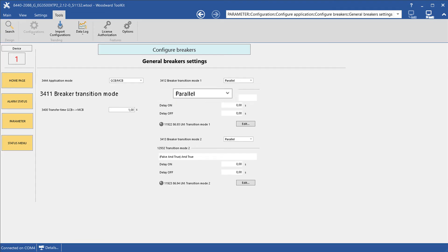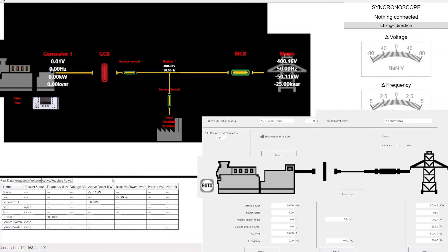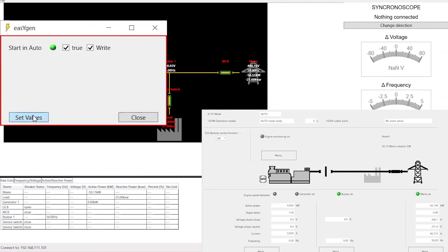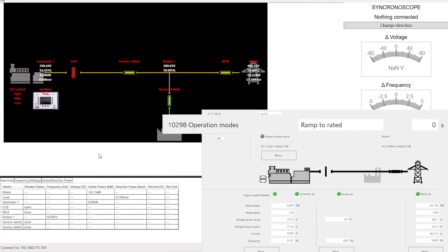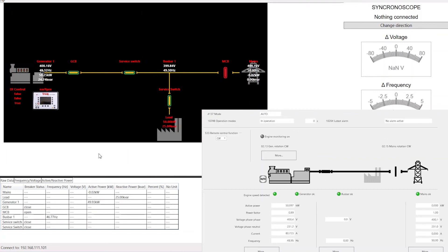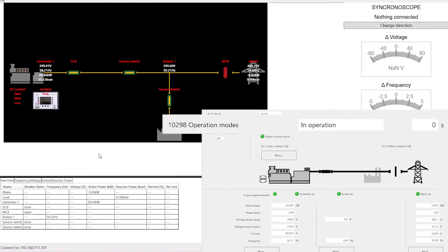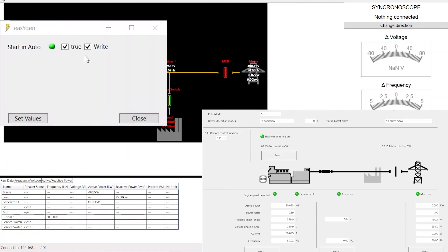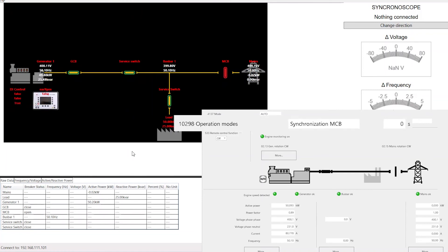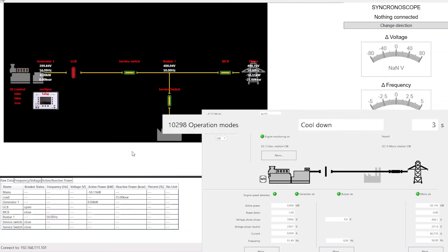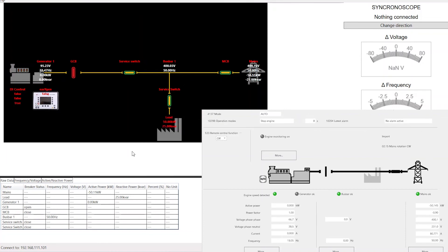The next breaker transition mode is closed transition. Again, the load is supplied by mains. When the genset receives a start command, the engine starts up and the generator ramps up to its rated values. When rated values are reached and monitoring is activated, the GCB is synchronized and the mains breaker is opened immediately after the closing of the GCB. The EasyGen is able to match a breaker closing time of less than 100 milliseconds. Now the load is fed by the genset. When the start request is removed, the EasyGen synchronizes the mains breaker and immediately opens the generator breaker. As we are only short time parallel, there will be no unloading of the generator breaker before it is opened. After opening the generator breaker, the load is again fed by the mains incomer only. The genset will go into cooldown and stops after the cooldown timer has expired.